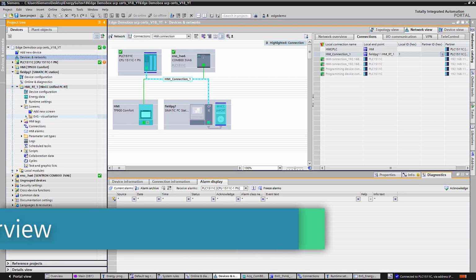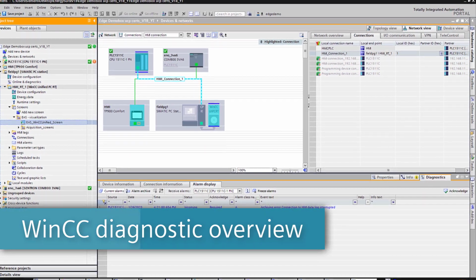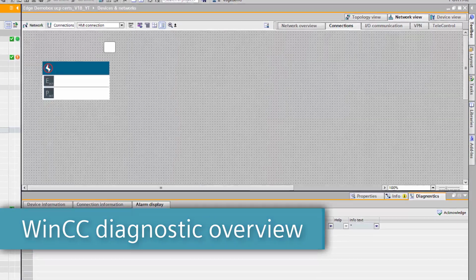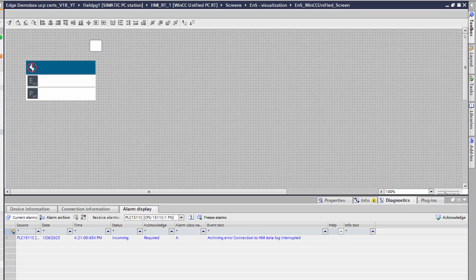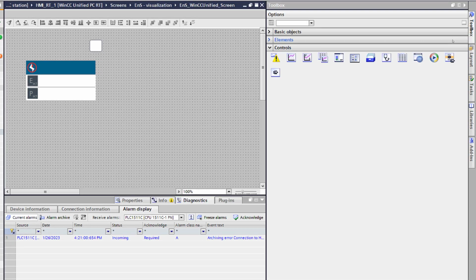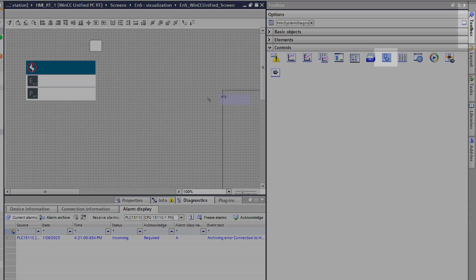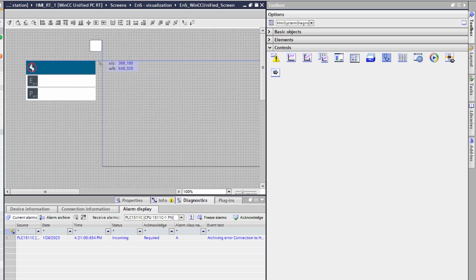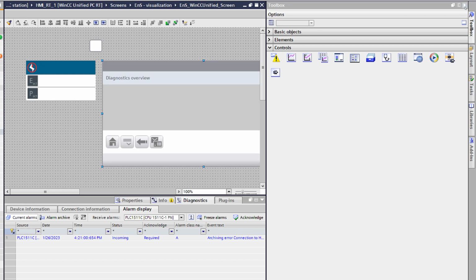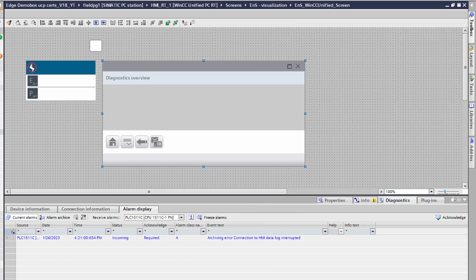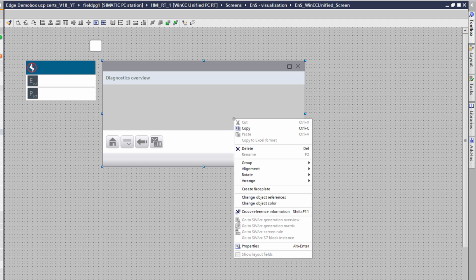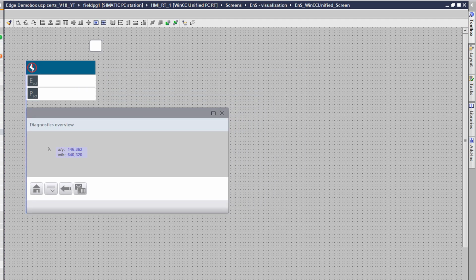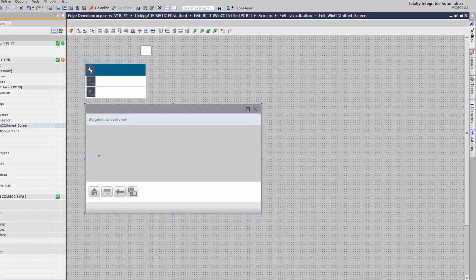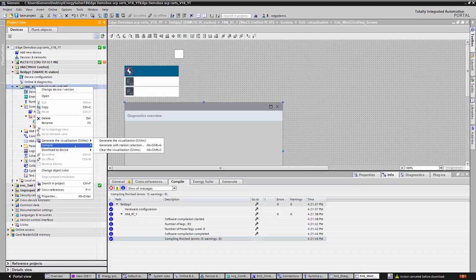For WinCC, we have a diagnostics overview. This overview can be applied from the toolbox. And under the control setting, look for the System Diagnostics overview. This is a drag-in tool. Once you drag it in, it's actually complete. There's nothing extra to program here. This overview taps into the central alarm management that comes directly from the PLC. This is also the central alarm management that we just saw in the diagnostics area of the PLC alarm display.